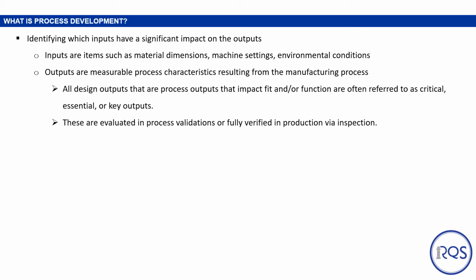When we identify which inputs have significant impact on the outputs, we are looking at the relationship between those inputs and outputs. Inputs are items such as materials, dimensions, machine settings, and environmental conditions, including time, temperature, pressure, voltage, process repetitions, etc. Outputs are measurable process characteristics resulting from the manufacturing process. Examples are dimensional requirements, pull strength, electrical resistance, etc. Design outputs that are process outputs that impact fit or function are often called critical, essential, or key outputs. These are evaluated in process validations or fully verified in production via inspection. Any features that we deem critical, we want to put more time and attention into processing to ensure that they meet requirements.